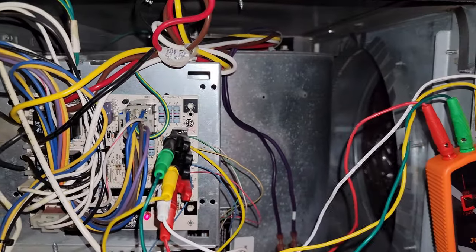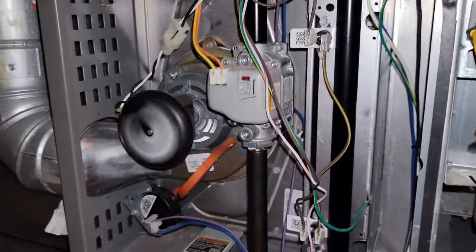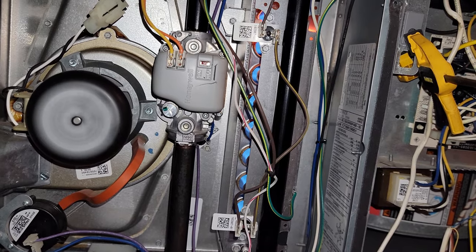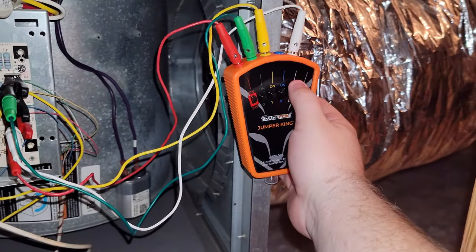Now let's test the cool cycle. You might not be able to hear it, but the condenser did come on and I can hear the refrigerant flowing through the line set. Last up is the heating cycle. I normally use a basic jumper for this between R and W, and my off switch was always just pulling the jumper off. Time for the new school tools. Everything is good, so let's hit the W switch and start the heat up cycle.